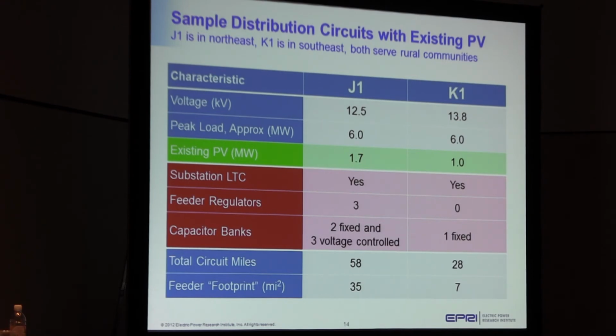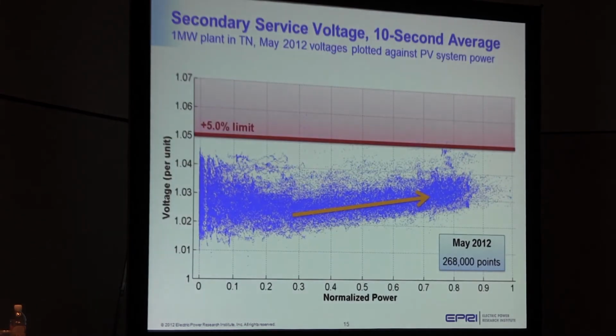You can see in the red bars substation load tap changers. That's the transformer making adjustments at the substation to regulate voltage. Then there are feeder regulators, which are devices on the distribution circuit out from the substation as you go down the line, and capacitor banks. So you can see these two circuits. We'll look at the 1 megawatt site first. This is again the same plant we've been looking at in Tennessee.